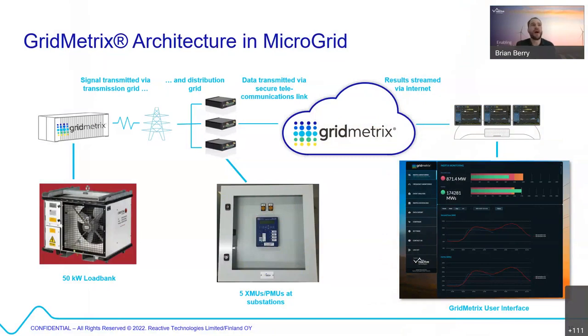So let's jump into some results. First of all, I'll talk about the architecture that was used in the microgrid. So remember, the total demand of that grid is around 20 megawatts, largely fed off pretty ancient diesel generators, north of Scotland. So not the fanciest equipment in the world, but they wanted to test the inertia in that system. They wanted to understand if they were running it adequately and expose any risks around their operation strategy. So what we did is the typical solution, we have a modulator.